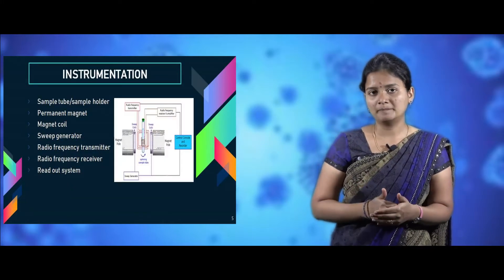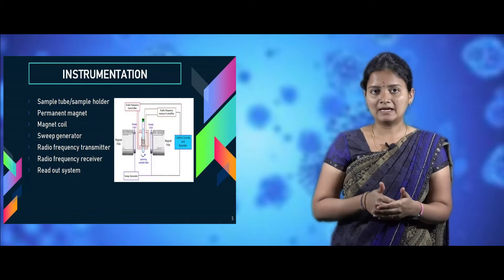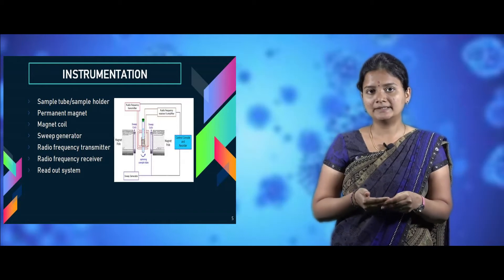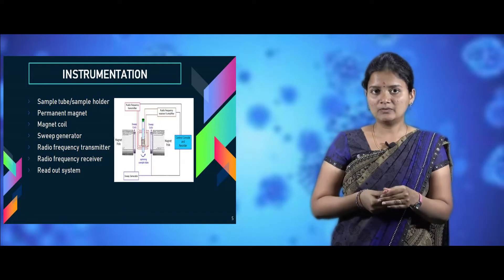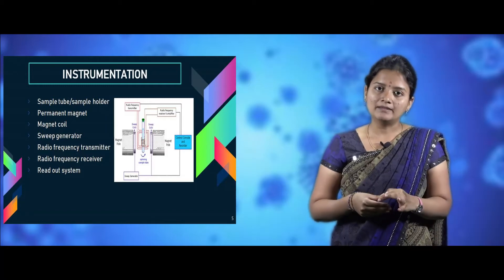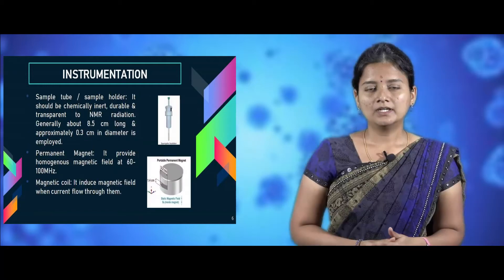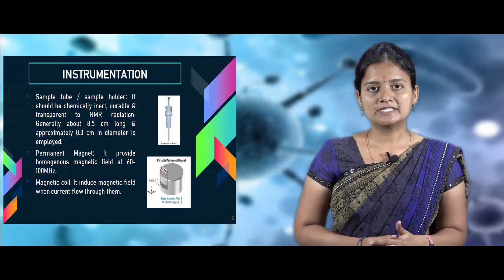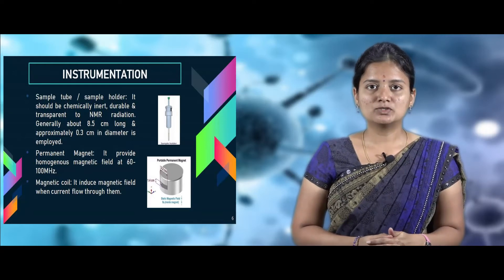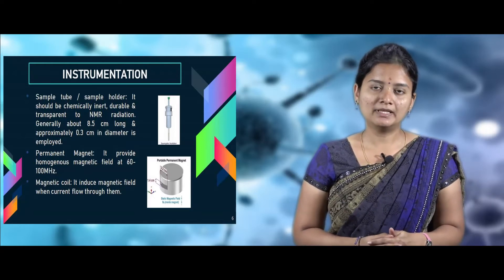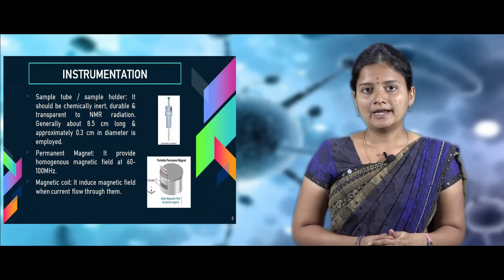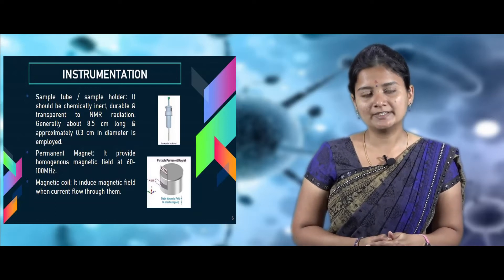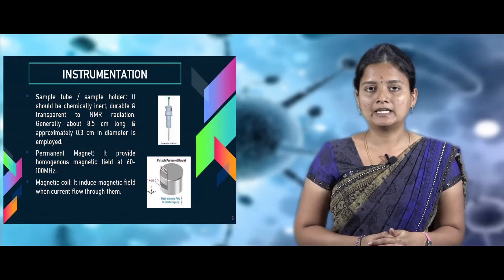The NMR instrument has a sample tube or sample holder, magnetic coil, permanent magnet, sweep generator, radio frequency receiver and transmitter, and a readout system. The sample tube must be chemically inert, durable, and transparent to NMR radiation. It has to be 8.5 centimeters long and 0.3 centimeters in diameter.